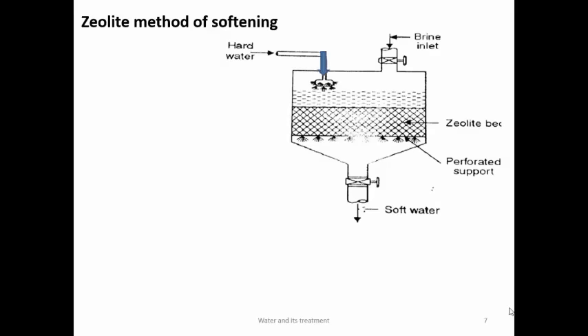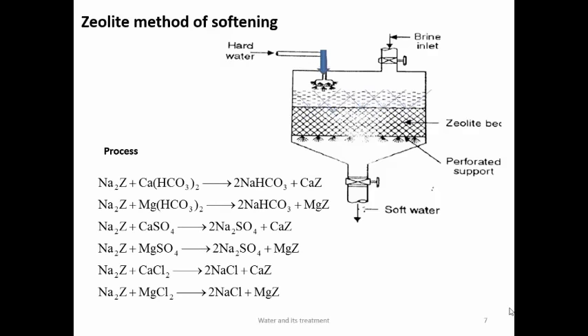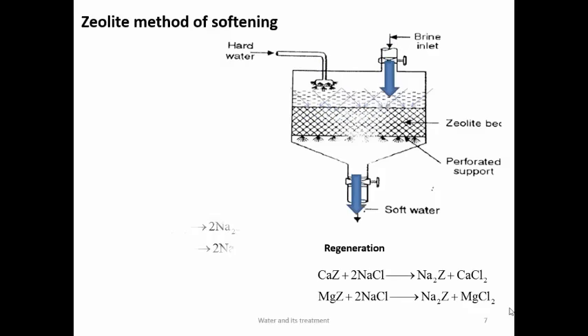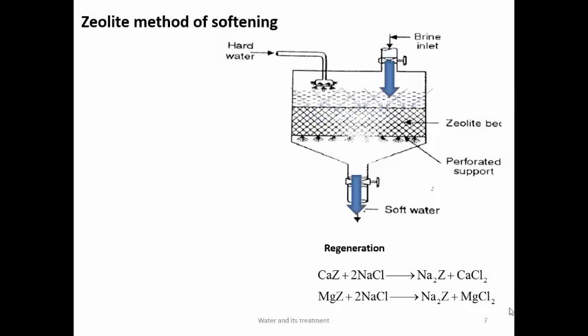Hard water is taken from one inlet and allowed to percolate through the zeolite bed. During this process: Na₂Z + Ca(HCO₃)₂ → 2NaHCO₃ + CaZ. Calcium is absorbed on the zeolite bed and soft water is removed from the bottom. After all impurities are replaced by Na⁺ ions, the zeolite bed gets exhausted. For regeneration, brine solution (10% NaCl) is added from the top and percolated through the bed; the reverse reaction takes place — Ca²⁺ is replaced by Na⁺, and Na₂Z is regenerated.